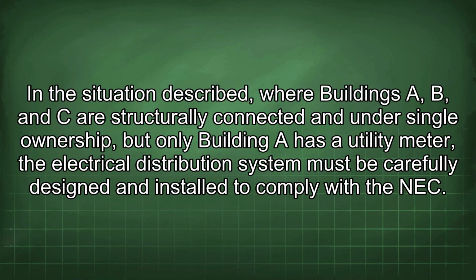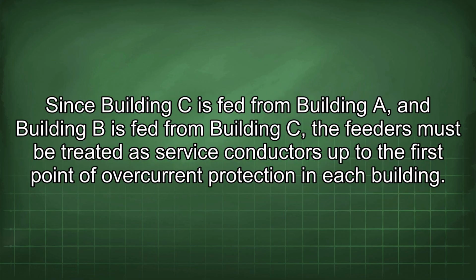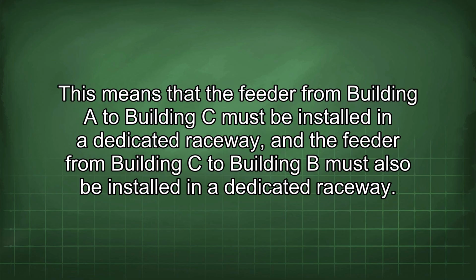In the situation described, where Buildings A, B, and C are structurally connected and under single ownership, but only Building A has a utility meter, the electrical distribution system must be carefully designed and installed to comply with the NEC. Since Building C is fed from Building A and Building B is fed from Building C, the feeders must be treated as service conductors up to the first point of overcurrent protection in each building. This means that the feeder from Building A to Building C must be installed in a dedicated raceway, and the feeder from Building C to Building B must also be installed in a dedicated raceway.